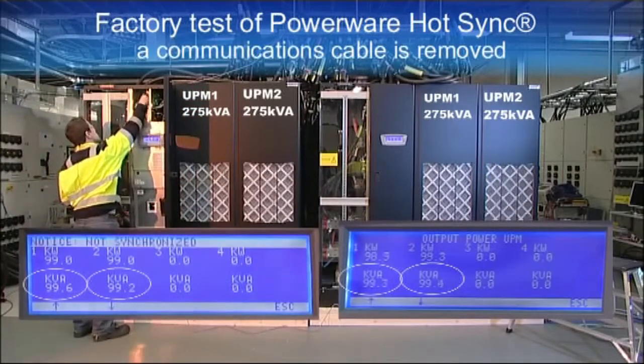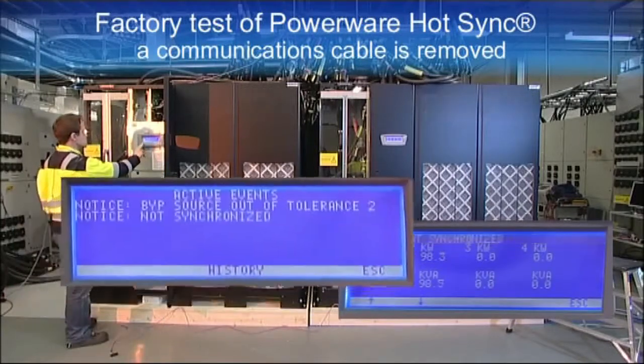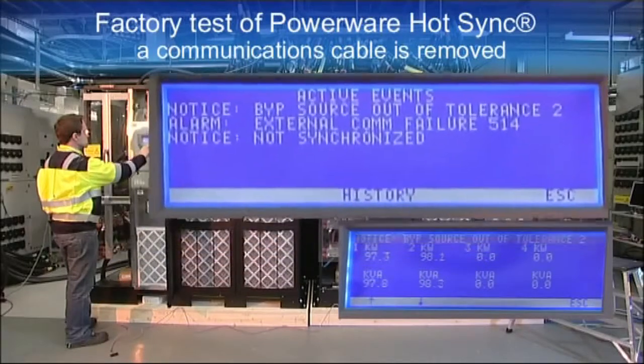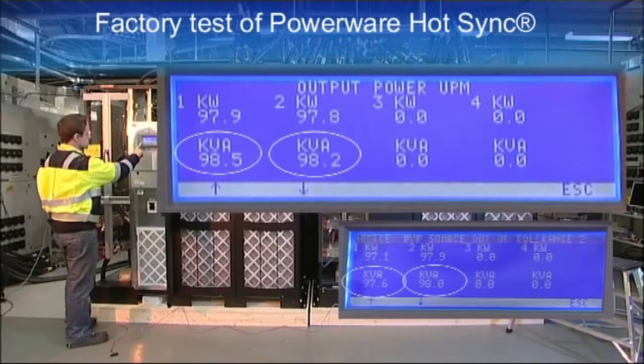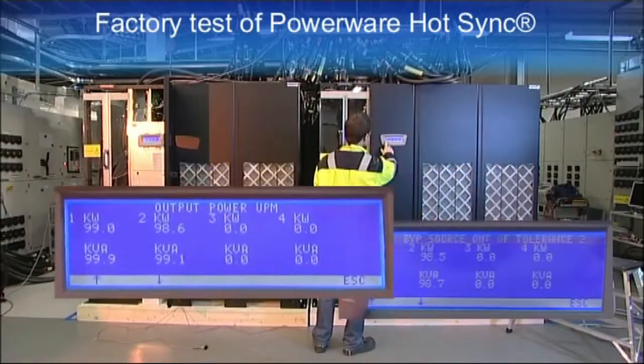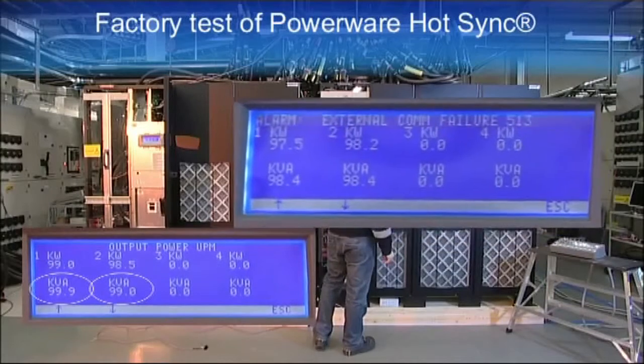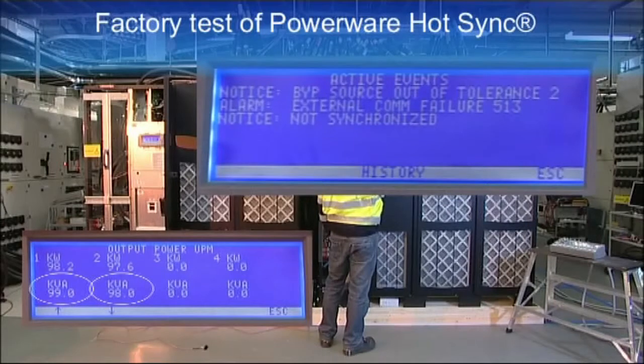What happens to the critical load if the communication breaks down? The inverter continues functioning normally and the load is shared evenly between the units. The units notice the communication breakdown and alarms are activated. Parallel communication error means that the communication to the other units is broken down.